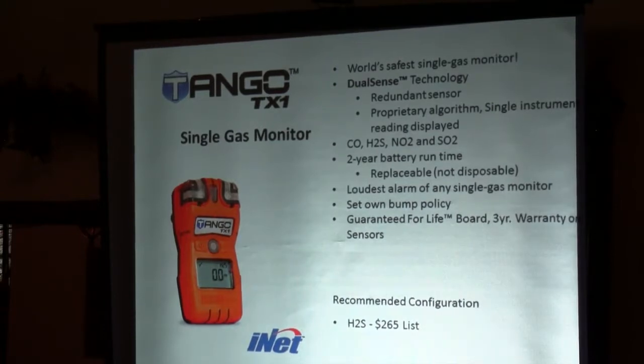Because we have redundant sensors, we are able to revise the bump test policy on this device: bump test whenever you want, calibrate every 30 days. You could just rent this from us or our distributors and send it back, and never have to worry about buying gas for it, putting gas on it, or doing that calibration process.